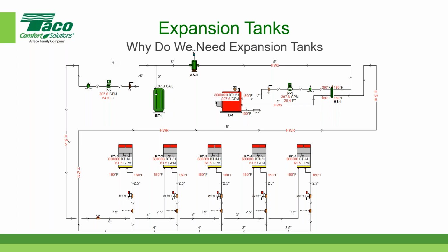How many gallons you fill expansion? How do you know? You have to calculate the volume of water that's in the piping system plus the equipment, plus the heat generating or the chilled water generating equipment. So in other words, if you had a 5-inch diameter pipe, you can look it up on tables. It says it has so many gallons per linear foot. You have to know the linear footage of all the piping in your system to calculate the gallonage.